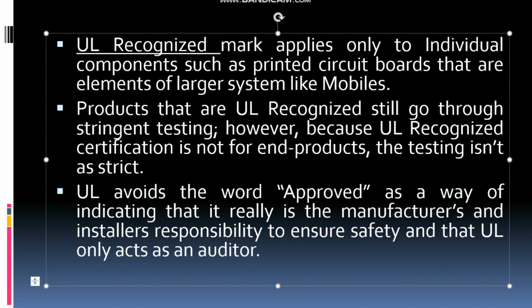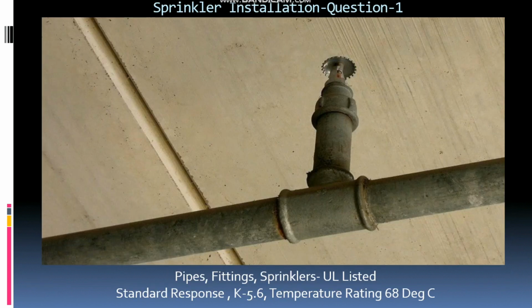The reason is that UL avoids the word approved as a way of indicating that it is really the manufacturer's and installer's responsibility to ensure safety, and that UL only acts as an auditor. So in this question, as I mentioned, the pipes, fittings, sprinklers, even the supports, everything is UL listed. But the problem is with the installation. UL cannot do anything with respect to the installation. It is the responsibility of the installer and manufacturer to make it happen.